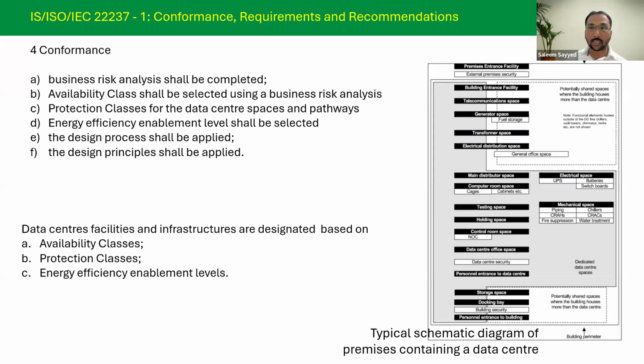Nowadays, as Mr. Rajendra very nicely said, the rack kilowatt is going up day by day. So cooling is also going up day by day. Nowadays, the good thing is that the manufacturers of servers, maybe HP or Dell, have come up with servers which can run on higher temperature. Earlier days, it was like 18 degrees, 20 degrees. Nowadays, people are talking about maybe 35 degrees cold air temperature. There's a very positive approach towards data center cooling now coming up.